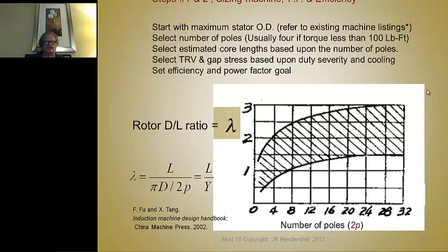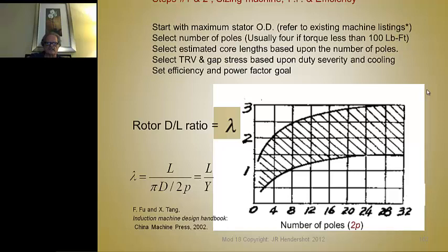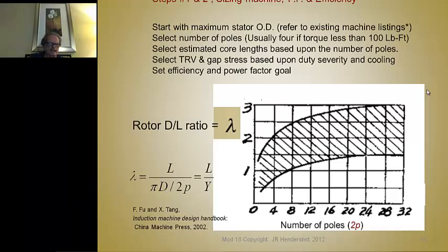The first thing we have to do is sizing steps one and two. This is based on the power factor desired and efficiency desired, so we start with the stator OD. We've already provided machine listings of the rotor diameter versus the stator diameter depending on the number of poles. Most induction motors are going to be four-pole machines unless we're designing really big ones. There's a relationship between the D-to-L ratio — the diameter of the rotor to the length — and there's a plot you can use to pick some starting ratios based on the number of poles.